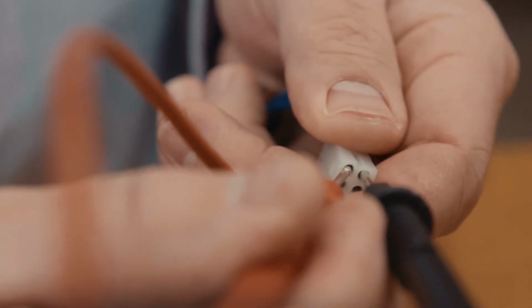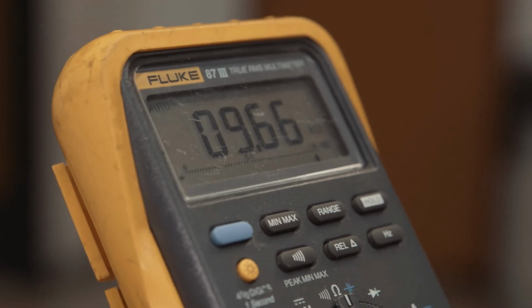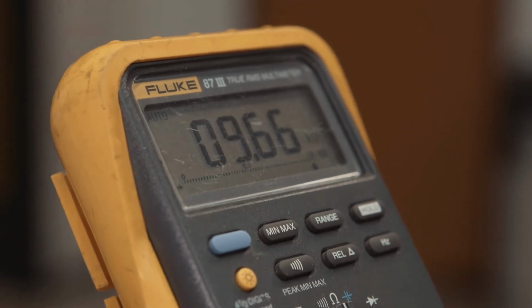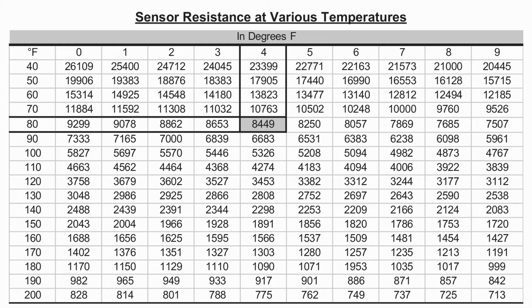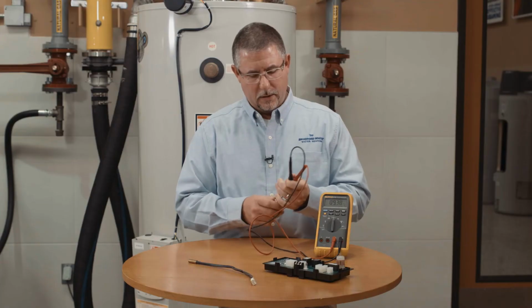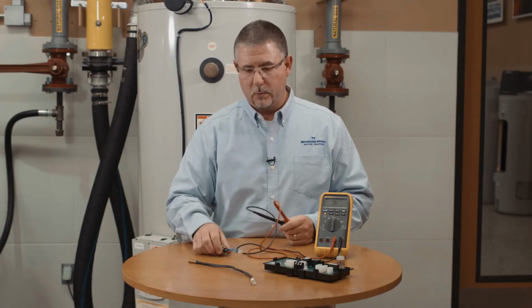As you measure resistance, it's going to give you a value, and that value will correspond to a number you'll find in the temperature chart in our service manuals. So for a 2-wire sensor, you measure wire to wire.